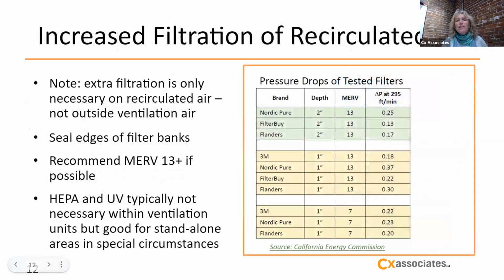The other thing that is really important for COVID and for viruses in general is to increase the filtration of the recirculated air. The ventilation air here in Vermont doesn't really need a special filter. It needs a rough filter, but it doesn't need a filter for capturing virus and particles from people, but the recirculated air definitely does. Typically an air handling unit will have a MERV 6 to 8 rating, and for viruses they are recommending at least a MERV 13, if not higher.